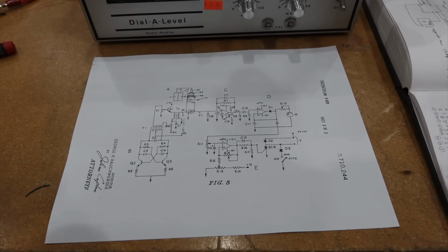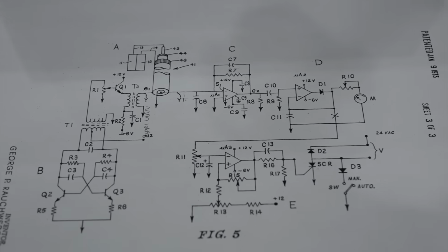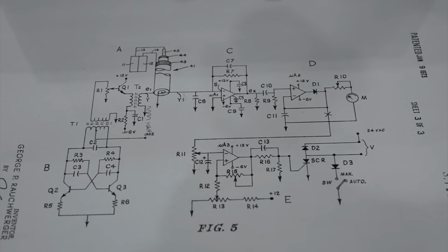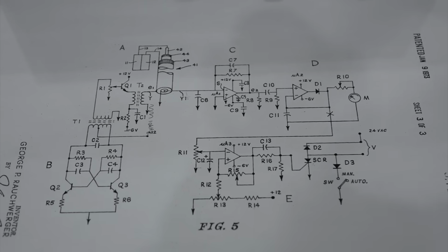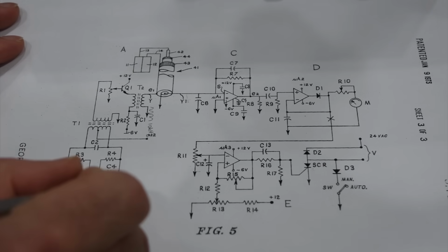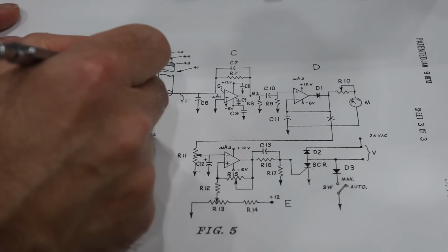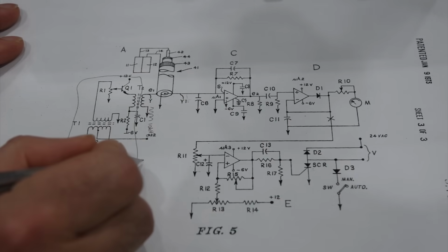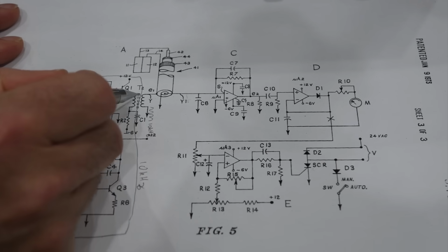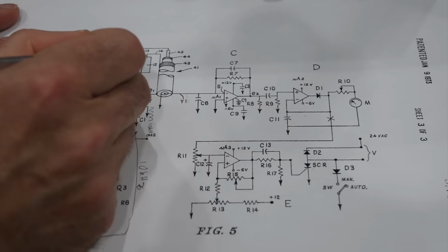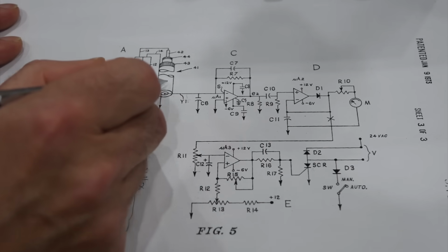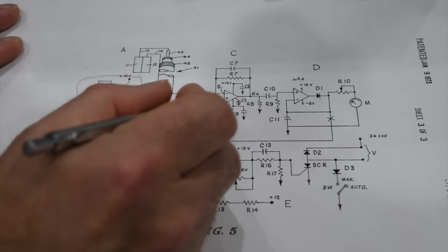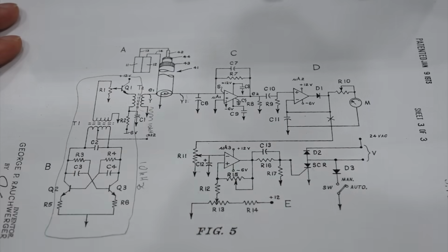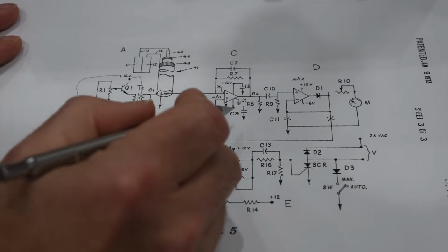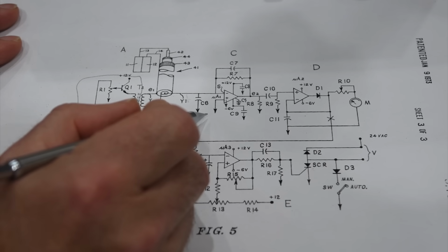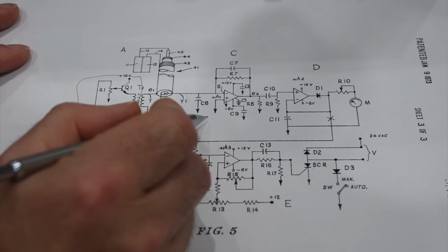And conveniently, one of the patents explains the electronics. Those are not the electronics that are in my box, but the blocks kind of resemble it, so it really helped me a lot. The principle is the same. So here you have first an oscillator, that's this portion right here. And that is just a 10 kilohertz sine wave oscillator that sends a signal into one end of the capacitive probe, then it comes back and you measure what comes out. And so here's the circuit that measures capacitance, and I thought for a second this is going to be complicated. So it takes a whole HP instrument to do it, but they don't have to measure absolute capacitance. They only have to measure relative capacitance, which is way easier.